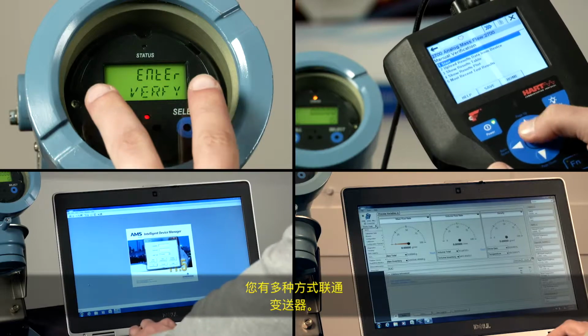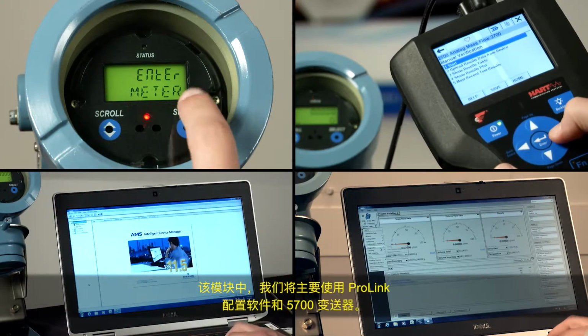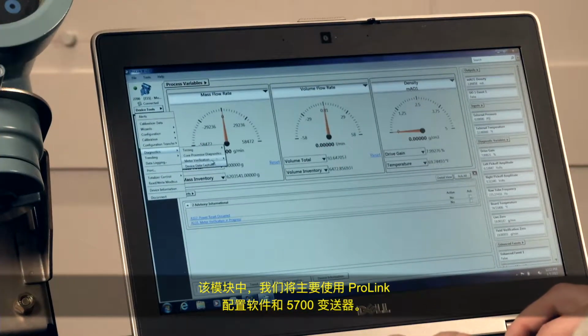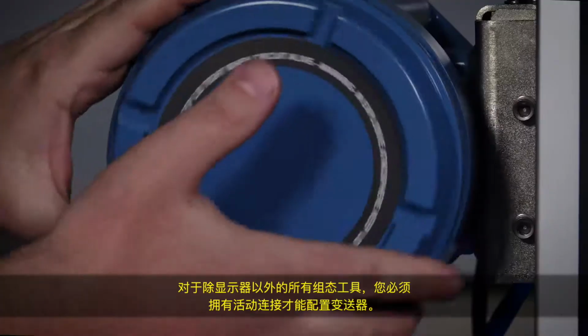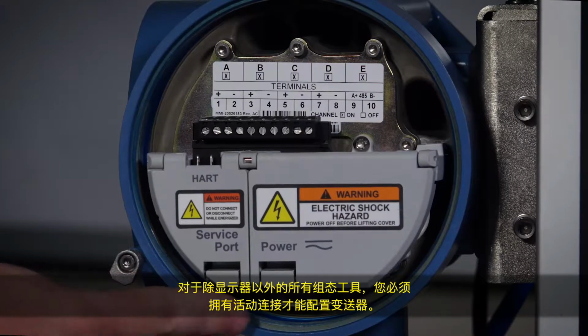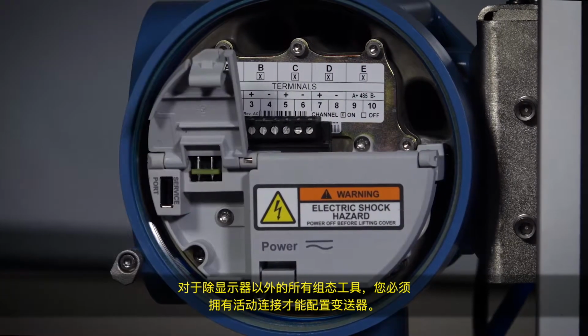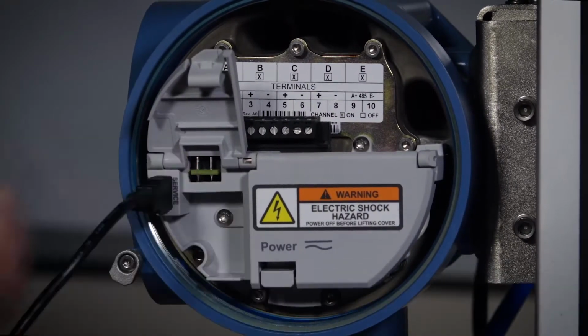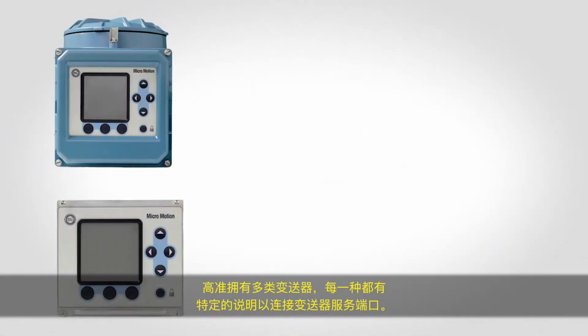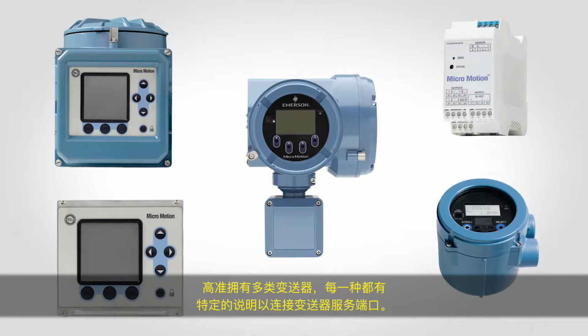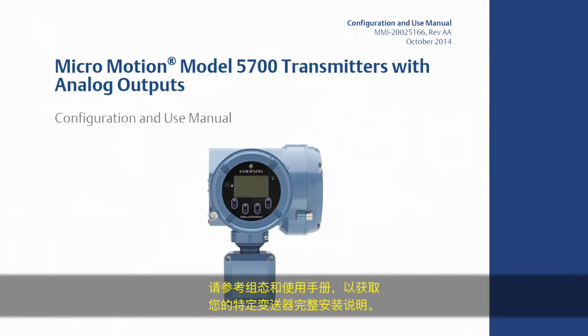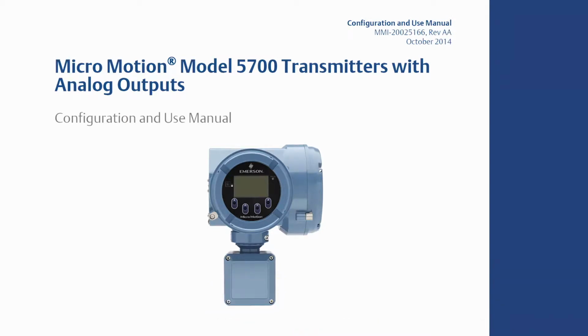There are many ways to communicate with your transmitter. We will focus on using the ProLink configuration software with a 5700 transmitter in this module. For all configuration tools except the display, you must have an active connection to configure the transmitter. MicroMotion has a variety of transmitters that each have specific instructions for connecting to the transmitter service port. Please refer to the Configuration and Use Manual for your specific transmitter for the complete setup instructions.